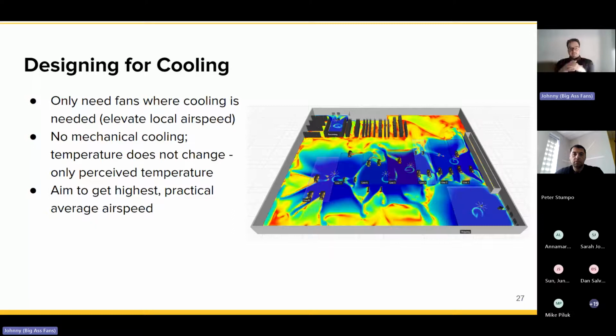Whenever we design a solution for cooling, a couple things we really want to know. Number one, where are the people? In this example, you're seeing a CFD model with racking towards the planned north side of that building. We likely wouldn't put fans in those racking aisles unless we know there's people constantly in that space, which that's usually a transitional space. So we're probably putting cooling where you're seeing these CNC machines or some kind of workstations.